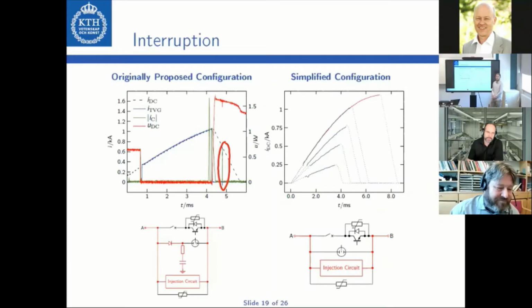It could be that something happened. It's quite surprising because there's nothing dynamically happening in the system at that point in time. So it's a bit surprising that there should be some noise coupled in, which could be by some di/dt or dv/dt. But at that time, as I said, all is relatively slow. So it's a bit surprising that there is some noise so late. I would have expected this more around the switching, so 4.1, 4.2 milliseconds, for example, but not at 4.8 milliseconds. But it was random, so to say. It would not always appear, and sometimes it appeared a bit earlier, a bit later. But I would expect that this is noise.